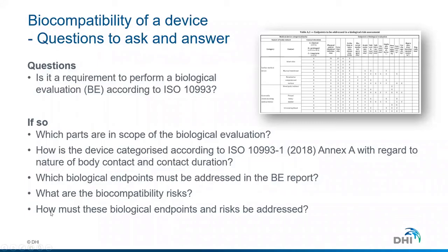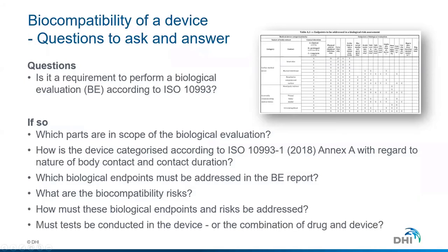And then you have to consider, how will I address these biological endpoints? How will I evaluate these biological risks? Which kind of data will I use? Will I use literature data? Will I use chemical characterization? Will I use toxicological approach, or will I use biological testing, either by in vitro methods or by animal studies? And the tests must be conducted in the final finished device or in representative parts of the device.